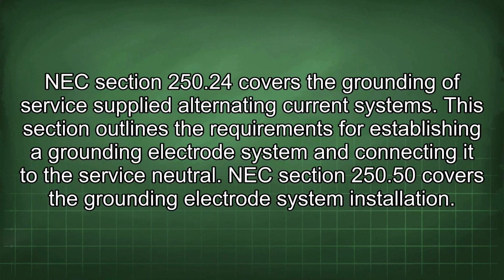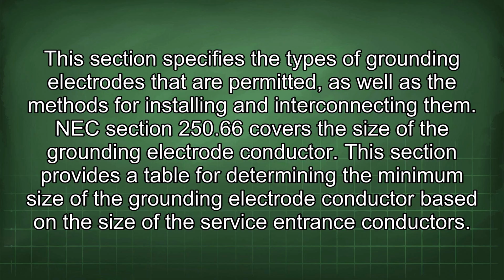NEC Section 250.24 covers the grounding of service-supplied alternating current system. This section outlines the requirements for establishing a grounding electrode system and connecting it to the service neutral. NEC Section 250.50 covers the grounding electrode system installation. This section specifies the types of grounding electrodes that are permitted, as well as the methods for installing and interconnecting them.